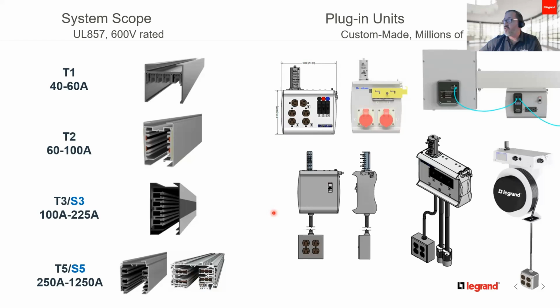However, just like you see in the image, we can couple our plugs with IP67 rated connectors at the bottom. So you have increased protection, not only on the plug-in unit or the busway on top, but everything that goes below that can have that additional IP rating protection. We've done that thousands of times, Doug, maybe?